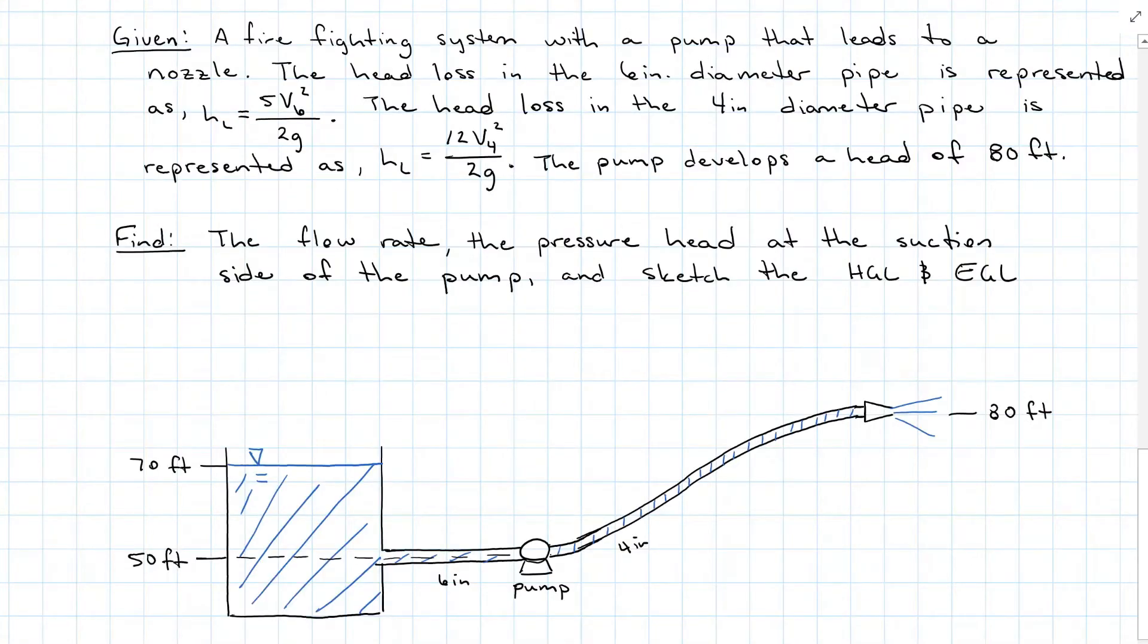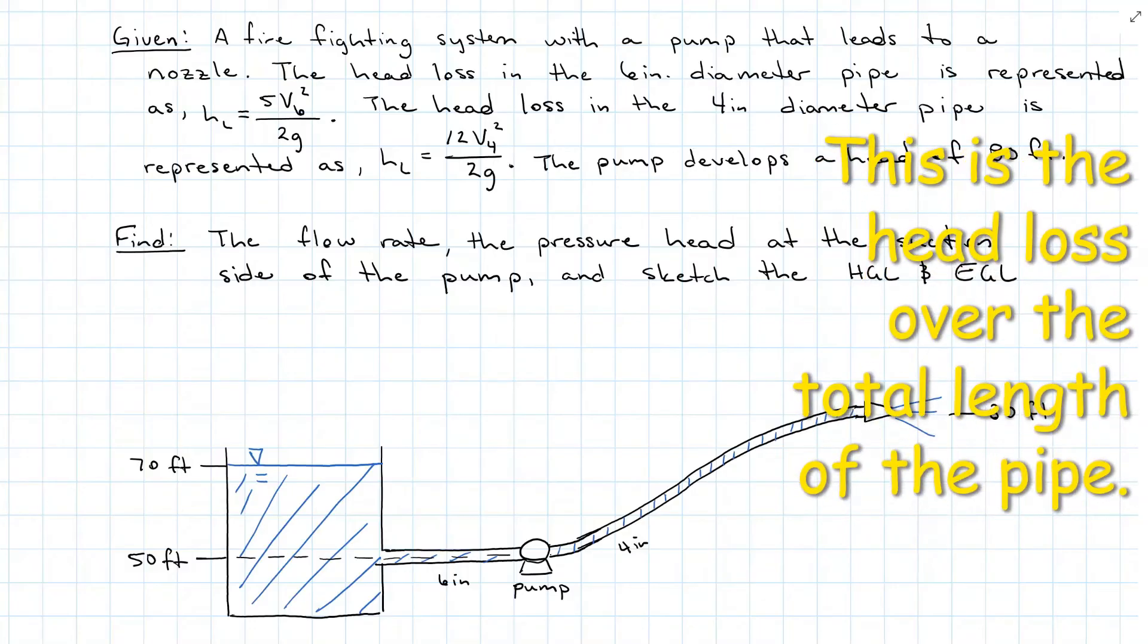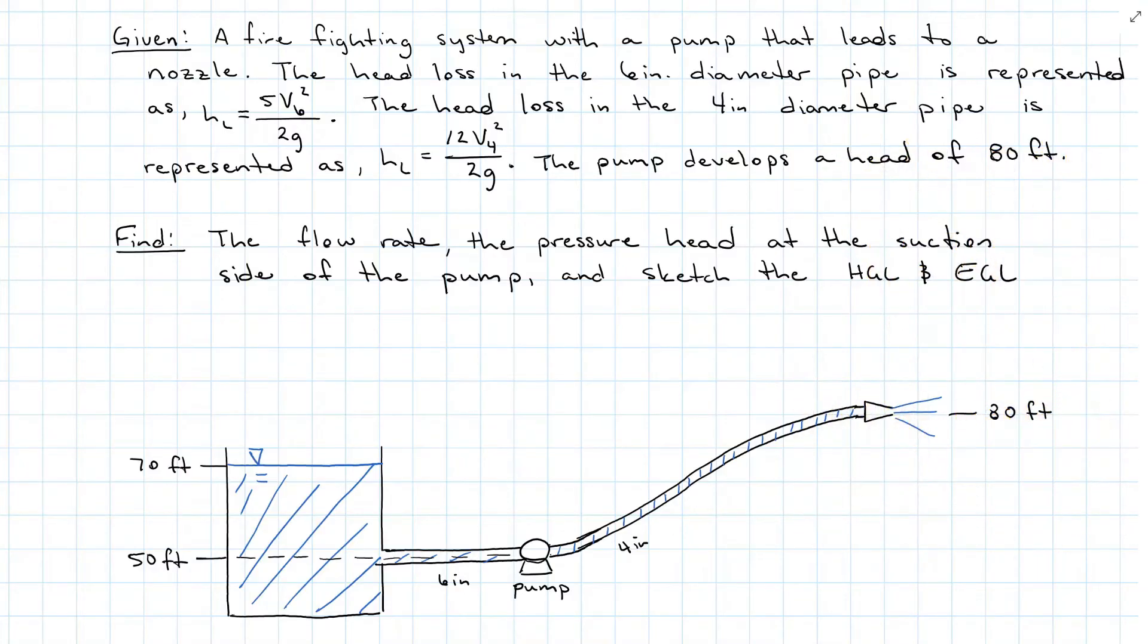For example, we have a firefighting system here that has a pump that leads to a 4 inch diameter pipe with a nozzle, and the pipe coming into the pump is 6 inches in diameter. The pump adds 80 foot of head, but we also have some head loss in our 6 inch pipe and 4 inch pipe. So that's given to us as equations for the velocity head. So the 6 inch pipe loses 5 times the velocity head, and the 4 inch pipe loses 12 times the velocity head over the length. We want to find the flow rate through the system, the pressure head at the suction side of the pump, and we want to sketch the hydraulic grade line and the energy grade line.